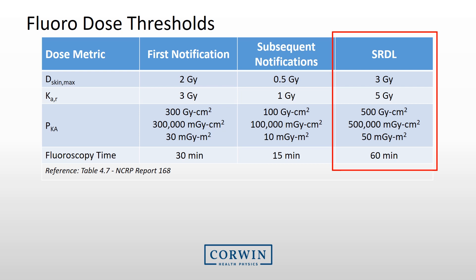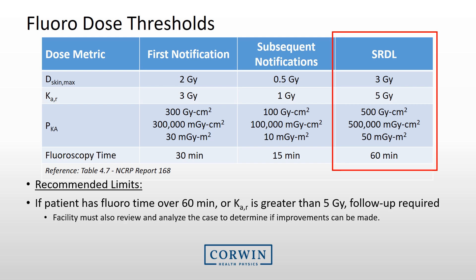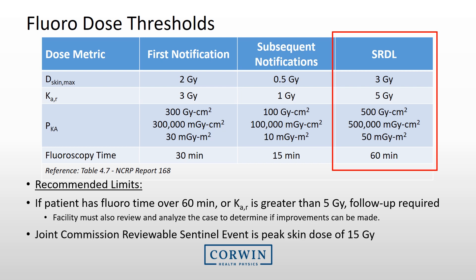It is recommended that the threshold for review and analyzing the event be set at a reported air kerma of 5 gray or a fluoro time of 60 minutes. The facility should follow up with the patient to assess for skin damage if the 5 gray limit is exceeded, and review and analyze that case to determine if improvements can be made. Also note that the Joint Commission considers it a reviewable sentinel event if there is a peak skin dose of 15 gray.